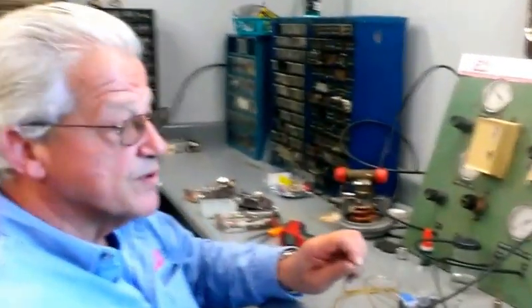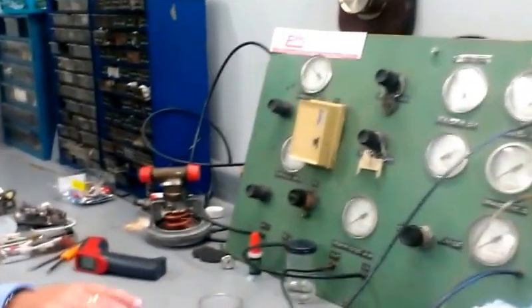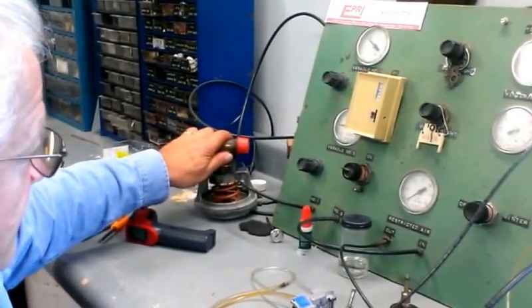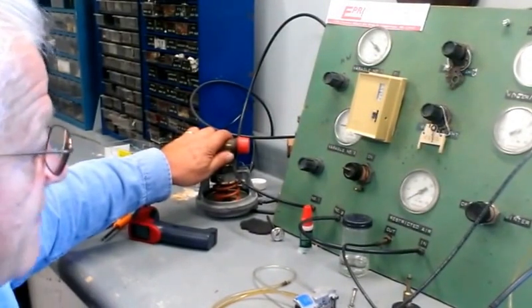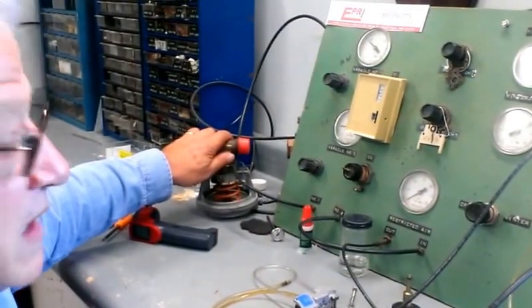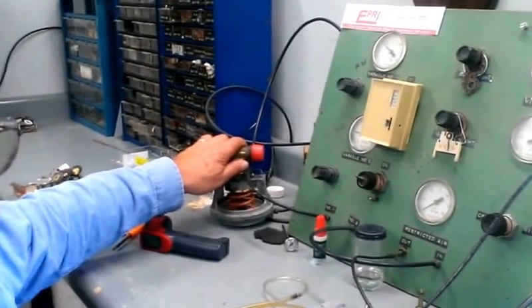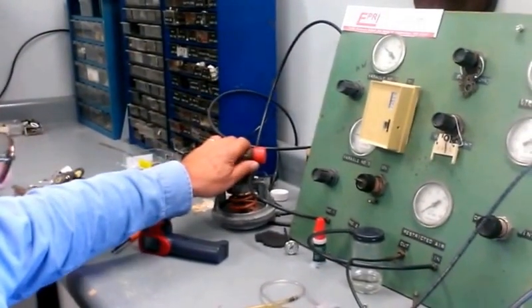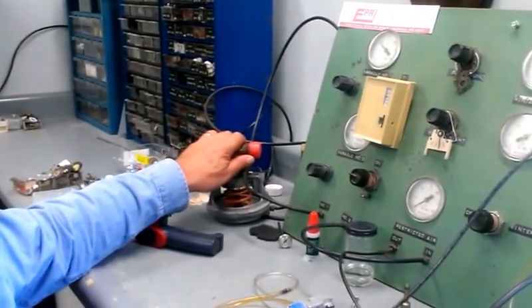I have my test board, and in my test board, teed into my branch line, I have an actuator here because the main function of the thermostat, aside from knowing what the temperature is, is to respond. An actuator doesn't bleed. It's got to bleed through the thermostat.